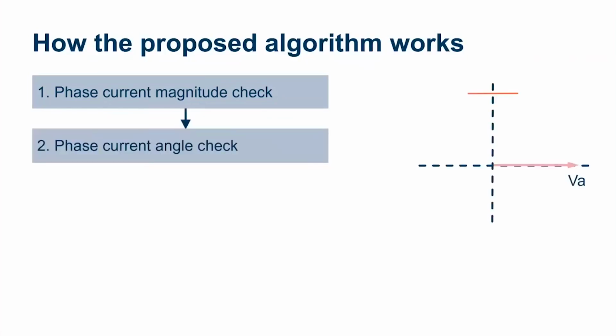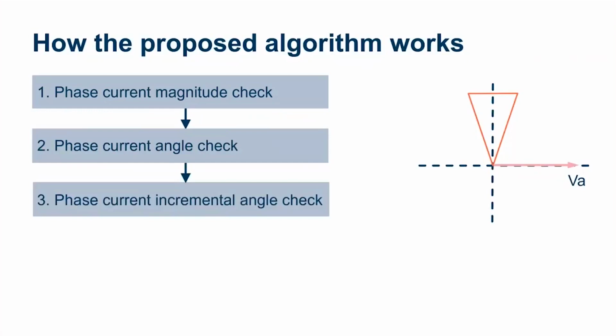The next thing we're going to check is the phase current angle. When we've got a broken conductor, we're just going to be reading the charging current, so the current should lead the phase voltage by about 90 degrees. We're going to be looking in this window to see whether our current has shifted to be within it. The next thing we check is whether we're seeing a change in our current angle. The reason we do this is that in low load conditions, checks 1 and 2 might be met, so we want to make sure that we're actually seeing a change from load current to this charging current. That's going to be our third check.